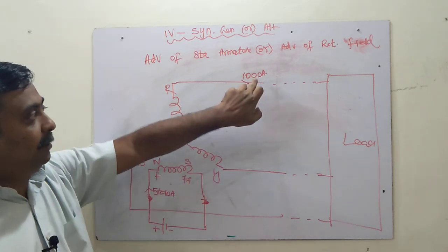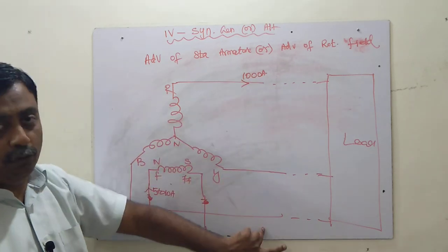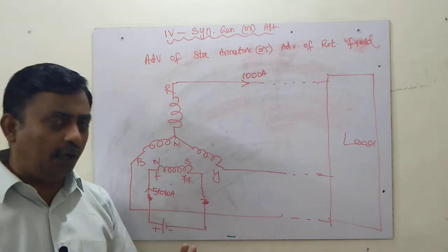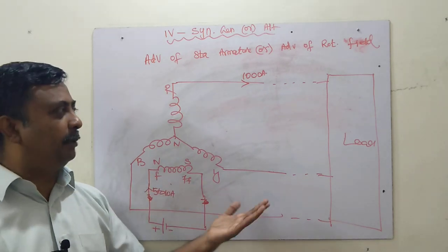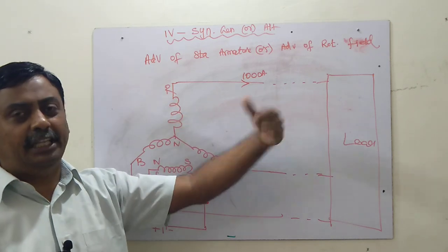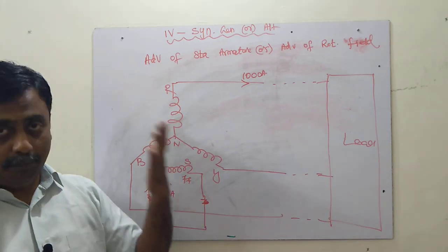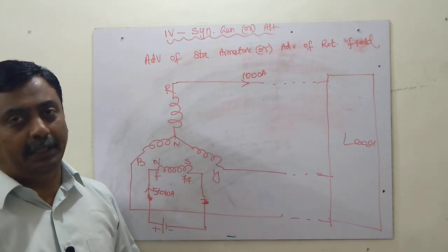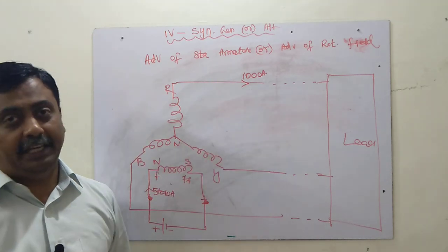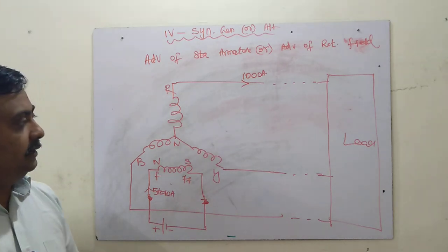A second advantage is the number of slip rings required. If we use a rotating armature (three-phase), we would need three slip rings and brush assemblies. But with a rotating field (DC supply), we need only two slip rings. These are the two major advantages. Additionally, cooling of the stationary armature is easier. These are the main reasons we go for a stationary armature.